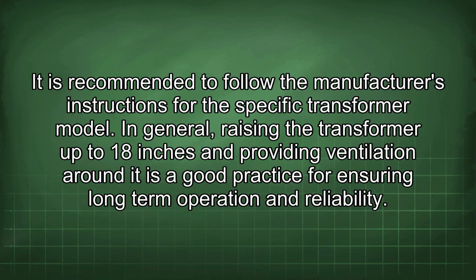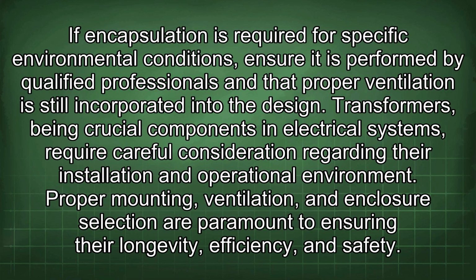It is recommended to follow the manufacturer's instructions for the specific transformer model. In general, raising the transformer up to 18 inches and providing ventilation around it is a good practice for ensuring long-term operation and reliability. If encapsulation is required for specific environmental conditions, ensure it is performed by qualified professionals and that proper ventilation is still incorporated into the design.